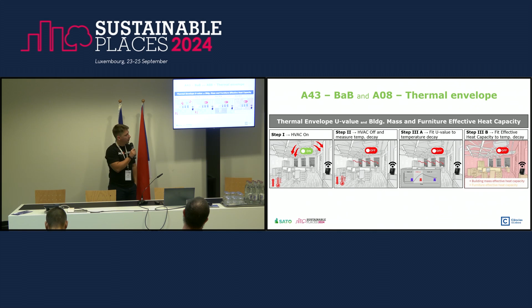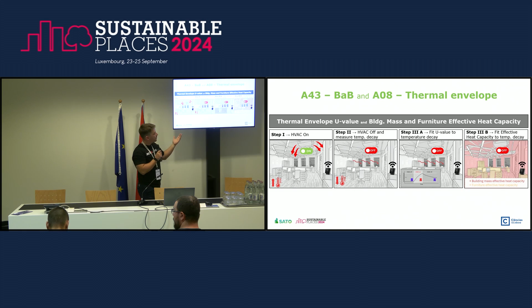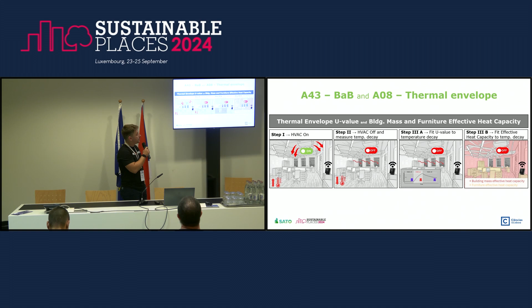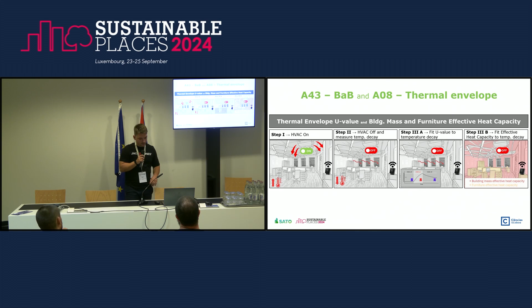Here you can see a visual representation of the actual deployment of the building-as-a-battery and thermal envelope assessments. We start by heating the thermal zone using the HVAC. Afterwards, we shut it down and let the thermal zone cool down, using this decay to fit the U value of the building envelope and the light and heavy effective thermal capacity of the building mass and furniture.